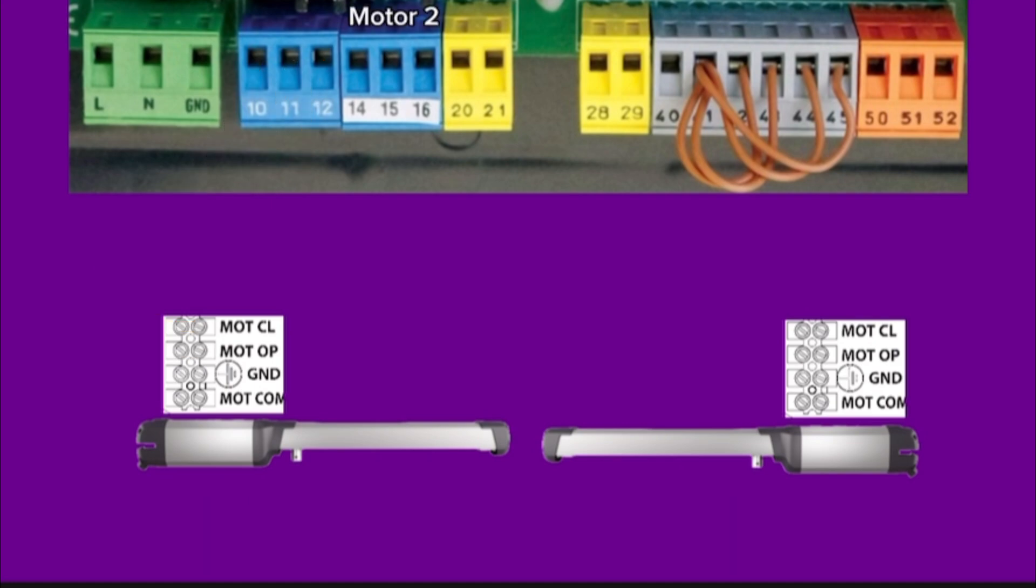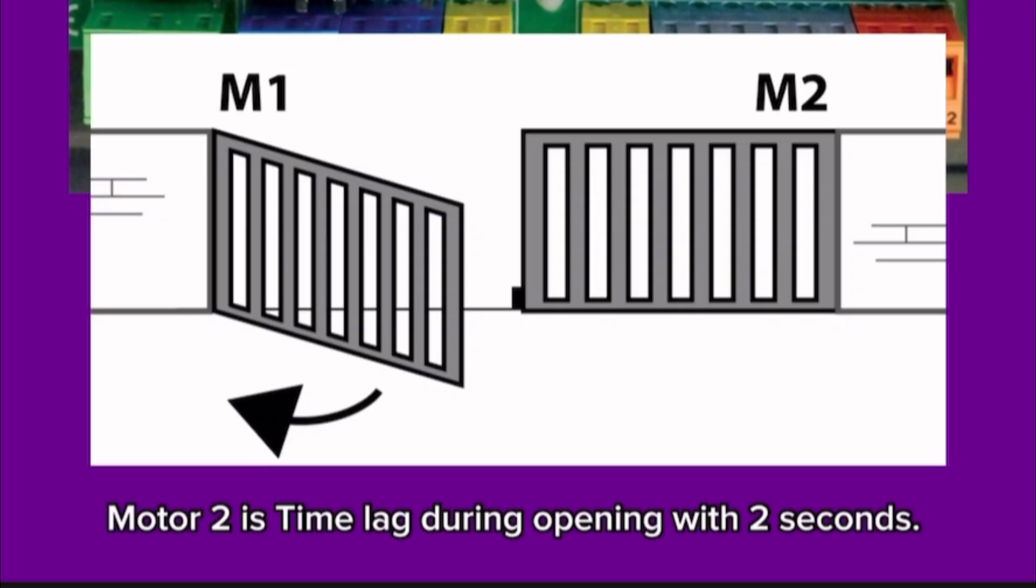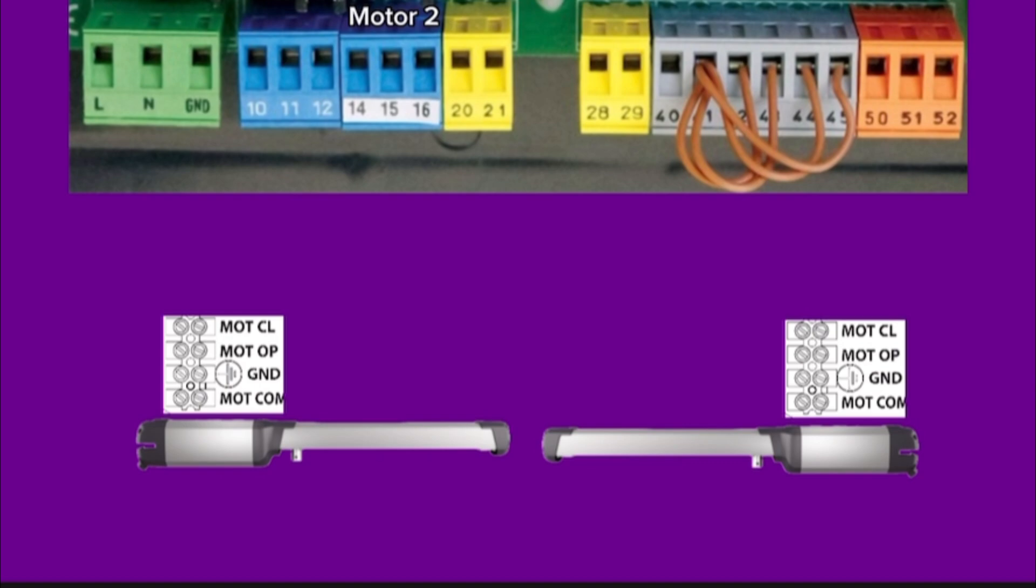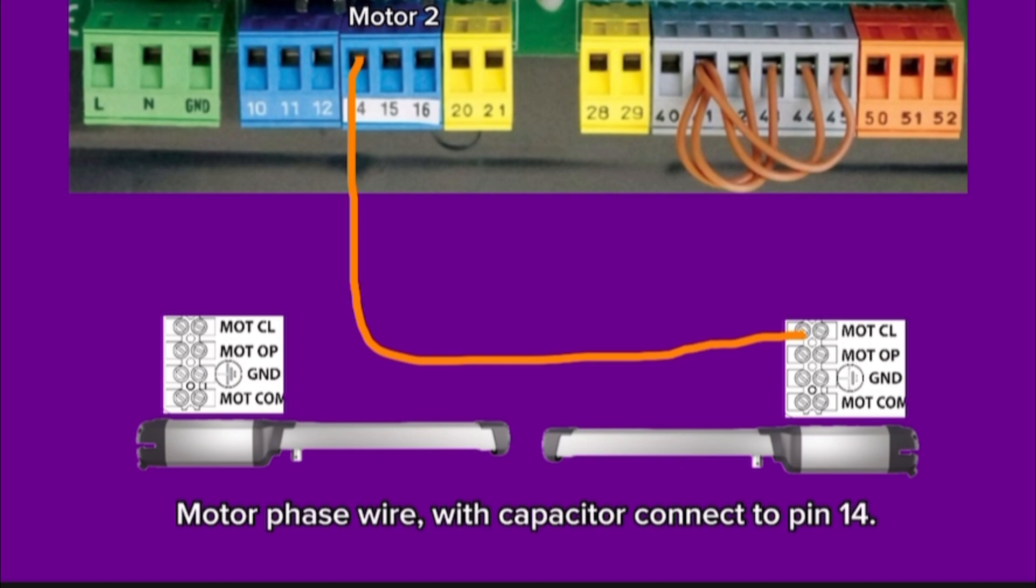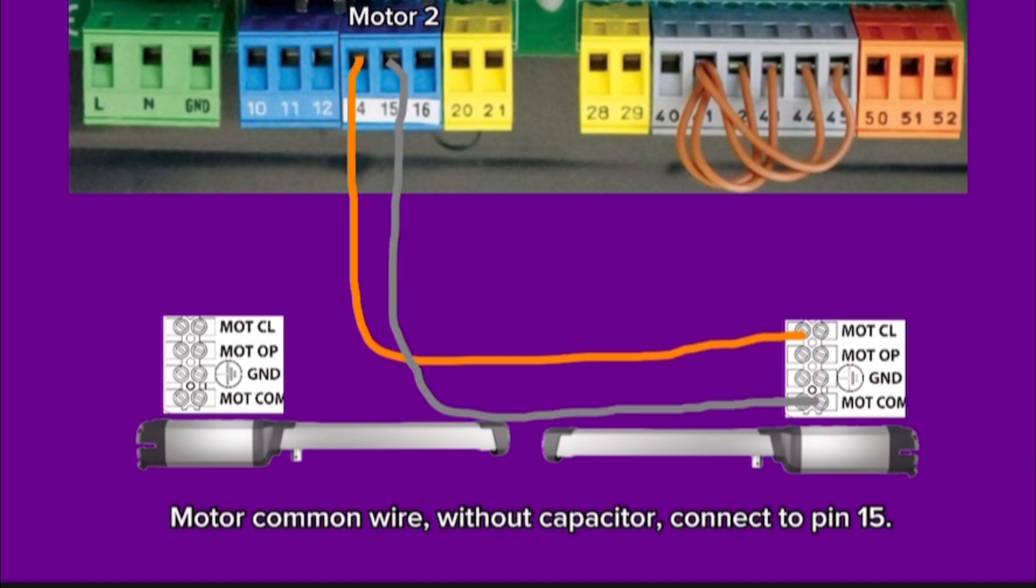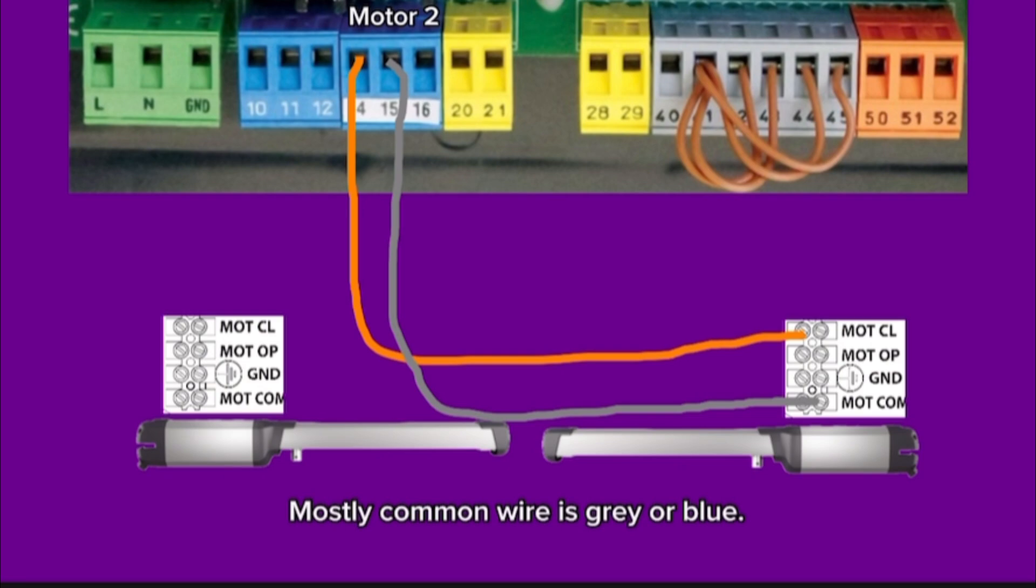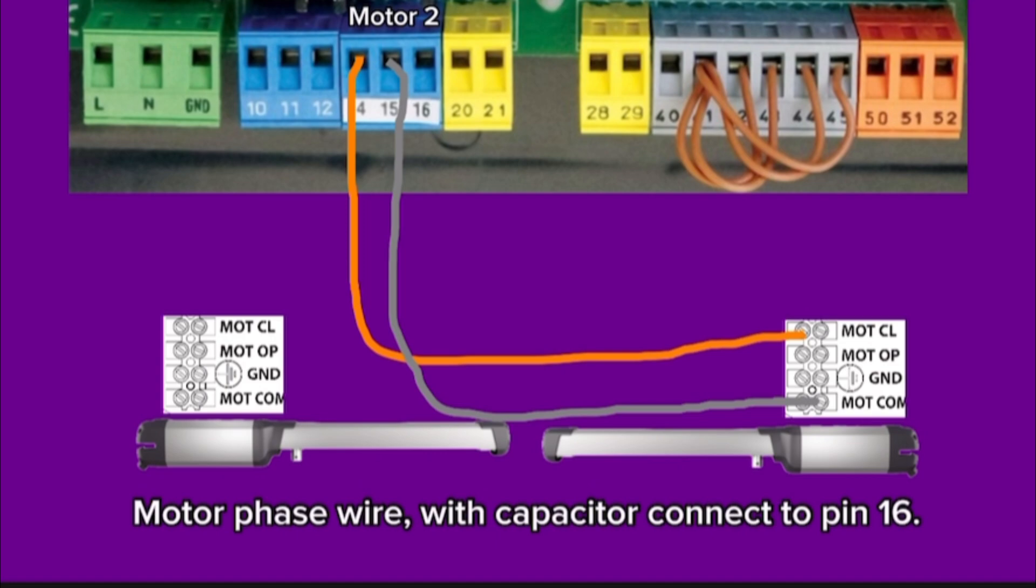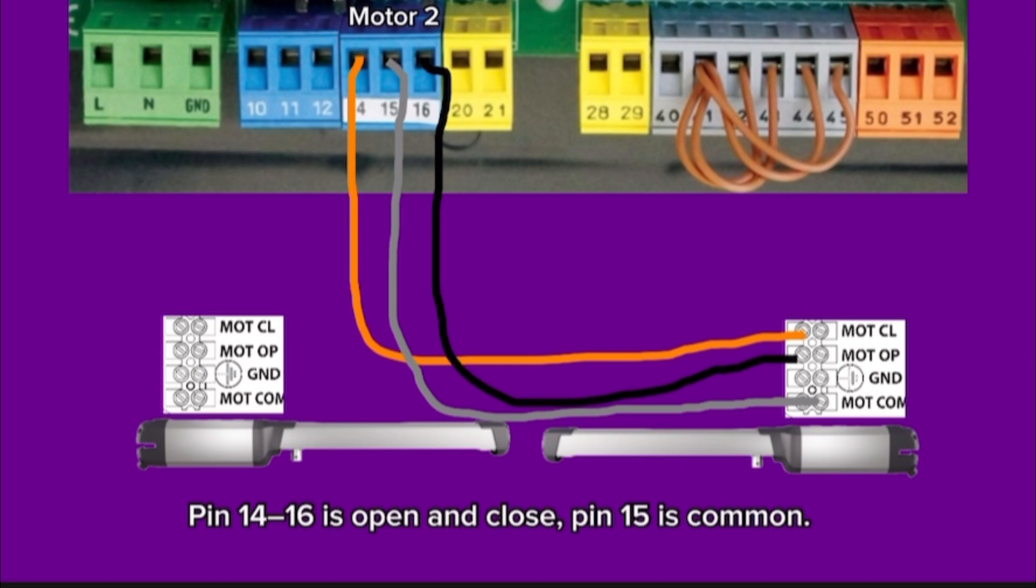Motor 2 connection. Pin 14, pin 15, and pin 16 are for motor 2. Motor 2 has time lag during opening with 2 seconds. Motor phase wire with capacitor connects to pin 14. Motor common wire without capacitor connects to pin 15. Motor phase wire with capacitor connects to pin 16. Pin 14 and pin 16 are open and close wires, and pin 15 is common wire of motor 2.